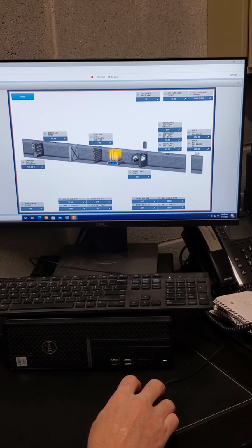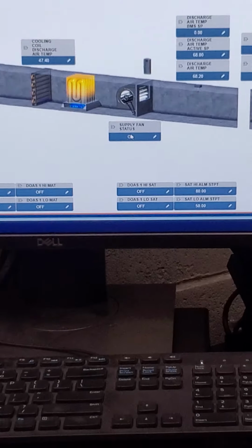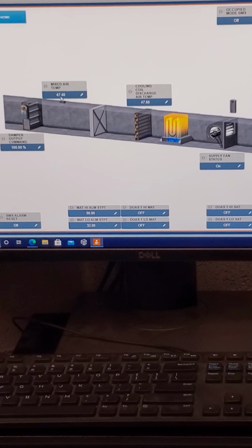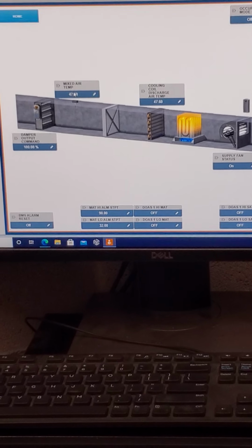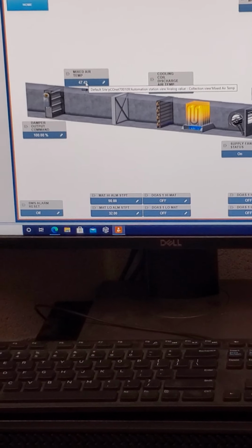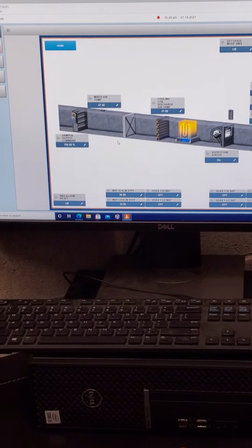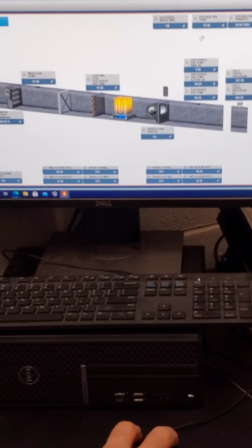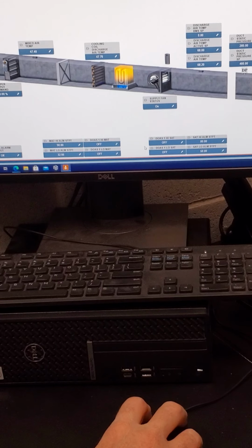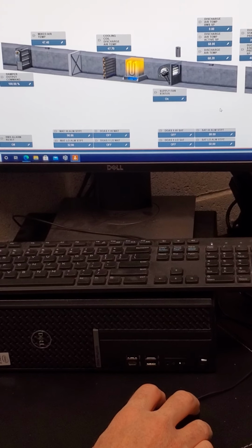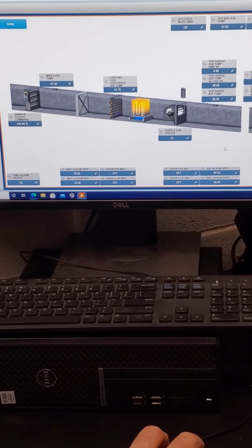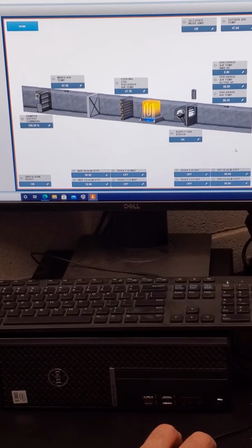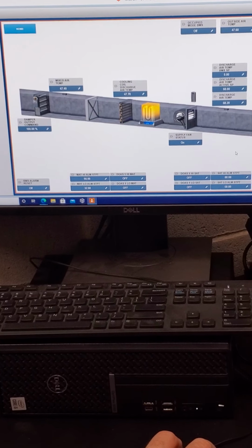So you can see your current temps, you can see the status of the fans, the leaving coil temperature. This point was called mixed air temp in the database, but I think it might actually be a return temp. Either way, it's not the DOAS unit. You can see these are all coming out of the third-party controller that's inside of the DOAS unit, so we're just kind of displaying them on the graphic. And they pretty much run themselves with the settings that are put in place.